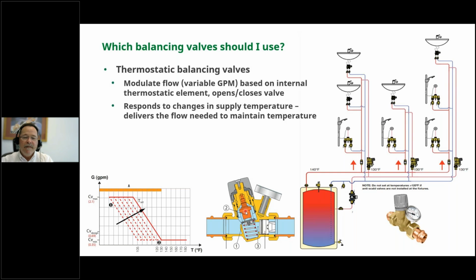It doesn't fully close ever, because there has to be a little bit of flow going across this sensor for the valve to be able to react to the system. So you can see here in the graph, when it closes down, it will reach what's called a CV, a minimum CV, and it will stay there as the temperature goes up. So that's what's different about it. It actually modulates and changes GPM in this system. And no matter which brand you buy, they're all basically the same kind of thing. They use a similar sealed wax element that opens and closes the flow path for this seat.